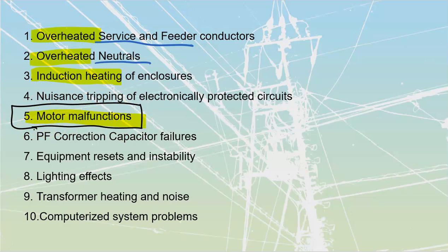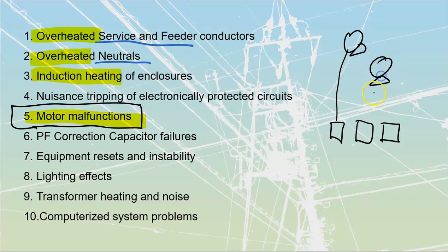It's usually one of the first places you tend to see problems inside of an industrial application. And usually it's one motor that just consistently gets screwed up. What I mean is this: you've got a bunch of different VFDs, usually somewhat close together inside of a centralized control station. Then you have a bunch of different motors throughout the plant, fed off of these VFDs. And these VFDs themselves are fed off of common feeders inside of that control room.